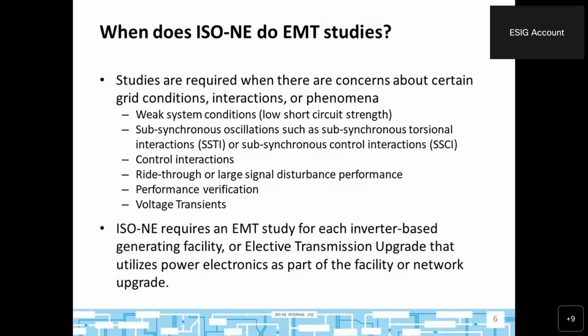We're also looking for the obvious things like voltage ride-through and other large system disturbance responses, like making sure the PLL stays synchronized, or the DC bus doesn't have an overvoltage condition which makes it trip, or that current limits are set properly so it doesn't trip for a design fault. We're obviously also looking for transients, it's kind of in the name, electromagnetic transients. We're making sure that there would not be trips for certain instantaneous overvoltages.